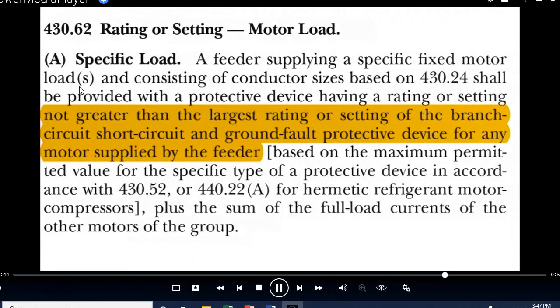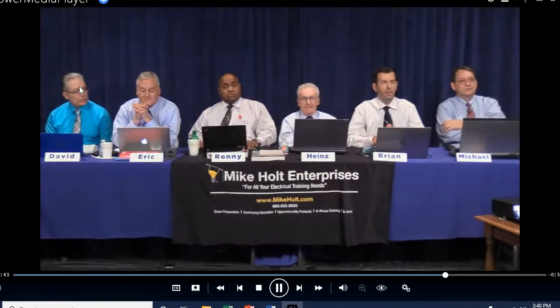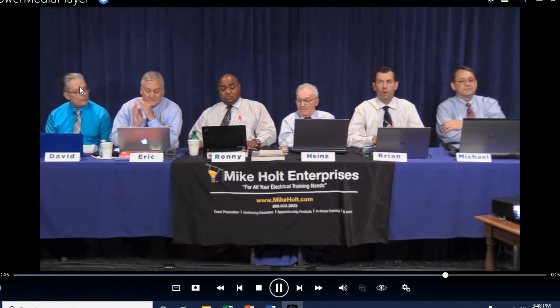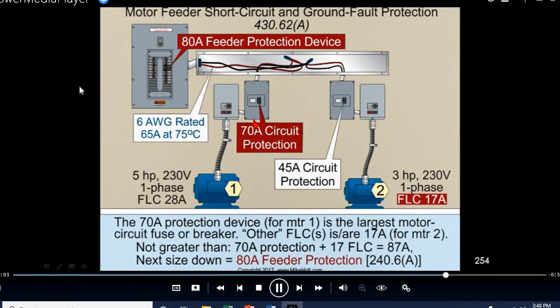Well, I think the simple thing that people are getting hung up on is that you've already added the buffer in there to start the biggest motor. So you have more than enough buffer in there for any motor that's smaller than the largest motor, no matter what you do. You use that same amount of buffer for any motor all the way down. Exactly right. The theory is this. You would need a 70 amp breaker to be sized to allow this motor to start. Is that right? Yep. You need a 45 amp breaker here to allow this motor to start.